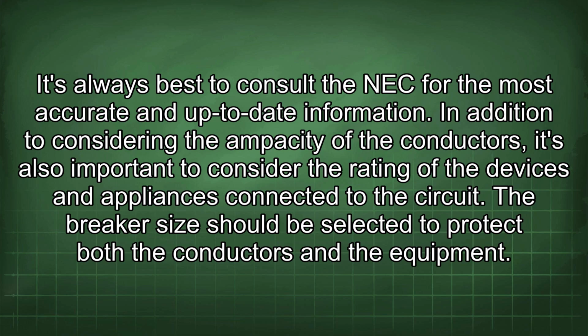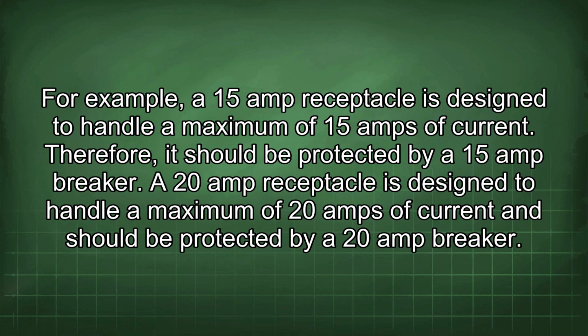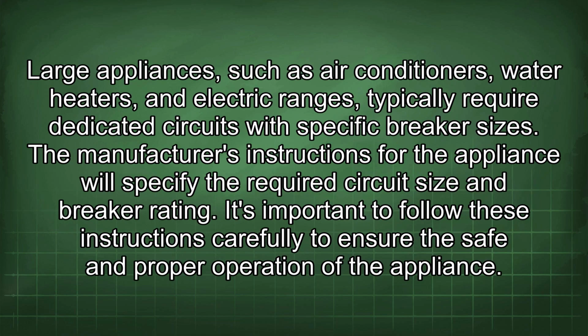In addition to considering the ampacity of the conductors, it's also important to consider the rating of the devices and appliances connected to the circuit. The breaker size should be selected to protect both the conductors and the equipment. For example, a 15 amp receptacle is designed to handle a maximum of 15 amps of current. Therefore, it should be protected by a 15 amp breaker. A 20 amp receptacle is designed to handle a maximum of 20 amps of current and should be protected by a 20 amp breaker. Large appliances, such as air conditioners, water heaters, and electric ranges, typically require dedicated circuits with specific breaker sizes. The manufacturer's instructions for the appliance will specify the required circuit size and breaker rating. It's important to follow these instructions carefully to ensure the safe and proper operation of the appliance.